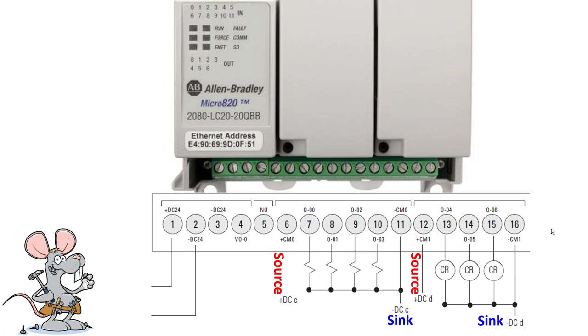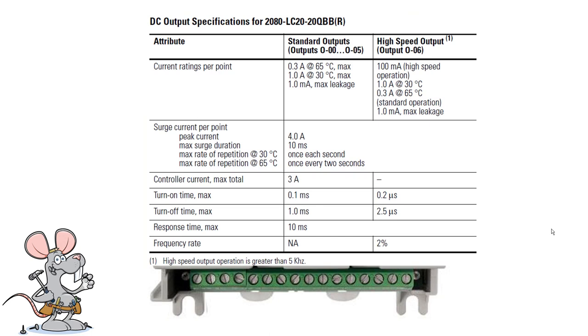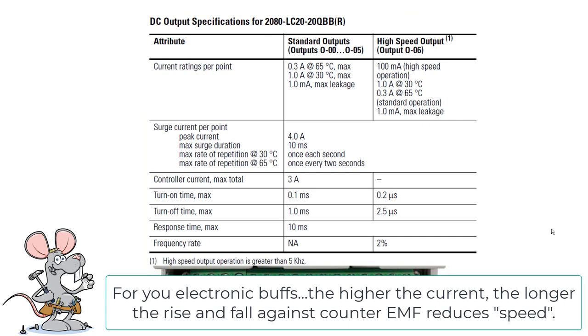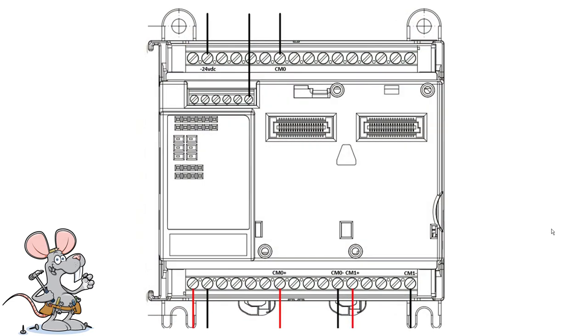For the outputs, you have a variety of choices. Some outputs are high speed and some are not. Notice that we have the plus connected to both commons — we're sourcing the loads. I threw this up here so you can see the current ratings on standard outputs zero through five — it's not high current. The high speed output is output six, at 100 milliamps. Looking at the wiring, the black wires are common or zero volts. Up on top you see minus 24 volts DC, common zero, and the six-terminal RS-232/485 strip. At the bottom you can see power coming in for the controller — red and black — with red going to the two positive commons and black to the two negative commons.